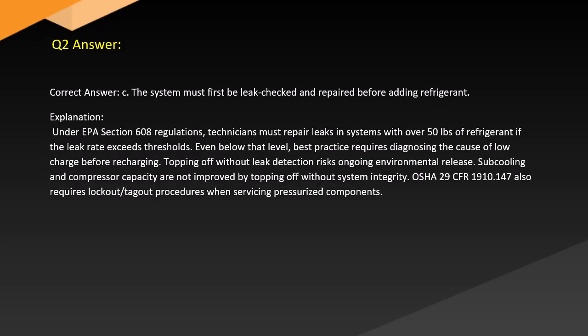Answer. Correct answer: C. The system must first be leak checked and repaired before adding refrigerant. Explanation. Under EPA Section 608 regulations, technicians must repair leaks in systems with over 50 pounds of refrigerant if the leak rate exceeds thresholds. Even below that level, best practice requires diagnosing the cause of low charge before recharging. Topping off without leak detection risks ongoing environmental release. Subcooling and compressor capacity are not improved by topping off without system integrity. OSHA 29 CFR 1910.147 also requires lockout/tagout procedures when servicing pressurized components.